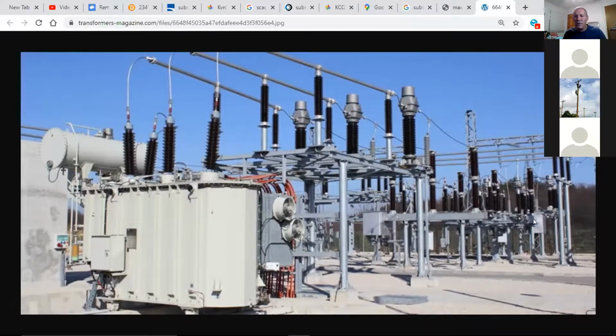If I have 4 breakers here, and let's say I've got 200 amps, 200 amps, 200 amps on all 4, which equals 800. Those CTs are going to give an 800 measurement for all 4 breakers. I should have how many amps on the outbound of the transformer? 800. There you go. It's comparing my CT reading from the transformer to all the breakers that are connected to it. If the 800 equals 800, everything's copacetic, and my 800 in conversion in the transformer is equaling what it should be on the high side.